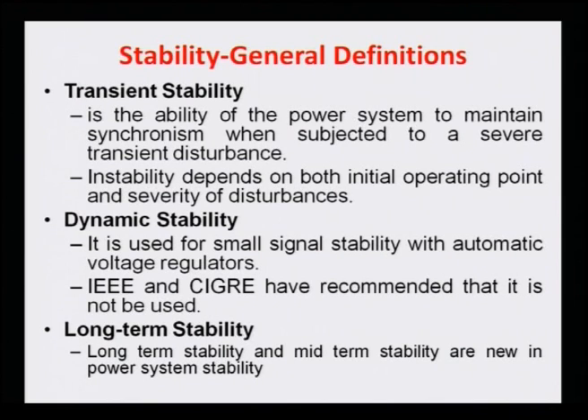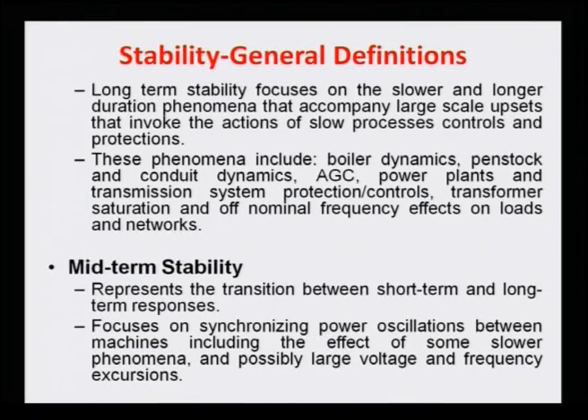Power system stabilities. So let us see what long term stability is. Long term stability and medium term stability are new in power system stability, because the transient is coming even in short term stability. Long term stability focuses on the slower and longer duration phenomena that accompany large scale upsets and invoke the action of slow processes, controls and protection. These phenomena include boiler dynamics, penstock and conduit dynamics, AGC (automatic generation control), power plant control, and transmission system protection and control. You can also include transformer saturation and off-nominal frequency effects on the loads and network variables. So here you see the larger dynamics, the machines being very slow, and mechanical dynamics like boiler dynamics and penstock and conduit system dynamics are also included, because the range of study is longer, and this is called long term stability.